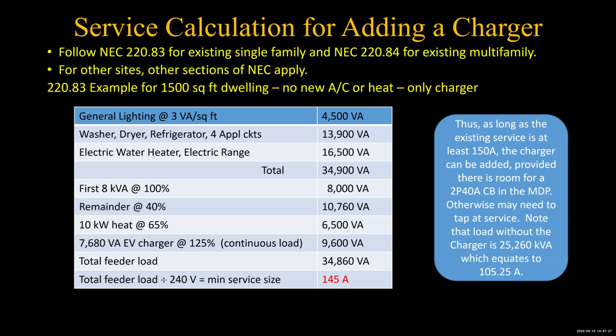Because it's 7680 volt amps, 7680 divided by 240 happens to be 32 amps. And that's why it's 7680. 32, 125% of that is a 40 amp circuit breaker. Okay. So if you can do that, you're good.